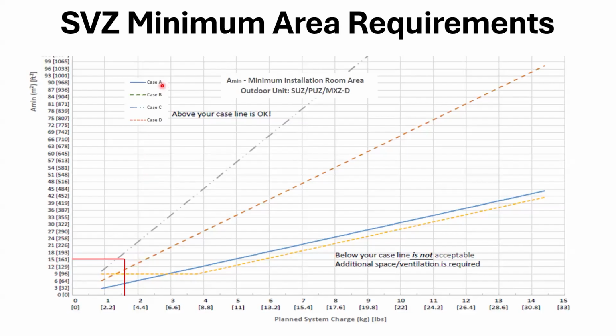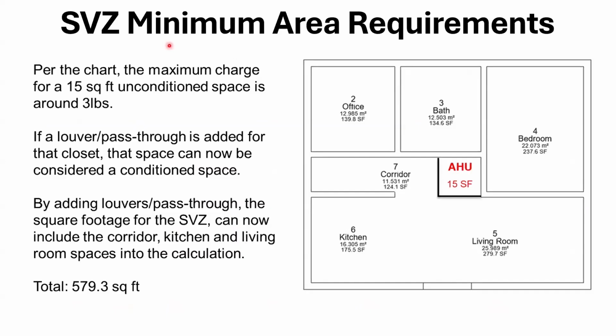We come over, we're on case C. That's this line right here. They're kind of off on that chart, but it comes down here and basically says 15 square feet coming across, and the charge we're allowed would be 3 pounds on this particular system. That's based on that unit being installed in a 15 square foot room with no transfer grills, anything, right? So per the chart, the maximum charge for a 15 square foot unconditioned space is 3 pounds.